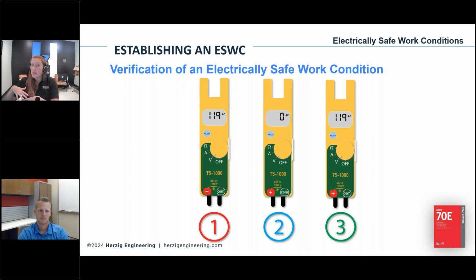He's got his PPE on and he's checking phase to phase, phase to ground. Everything's good. It all says 0. He goes back and unplugs the fan again, and the outlet's reading 0. He's like, what? So he plugs the fan in, it still turns on. Obviously there's power there. Tries again. He's like, okay, nope, my meter's not reading it. He wiggles it around. He's like, maybe I'm not getting a connection. Nope, can't get it reading. The meter's just stuck at 0.